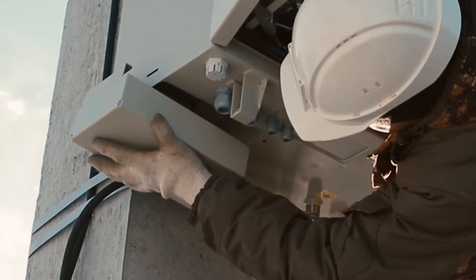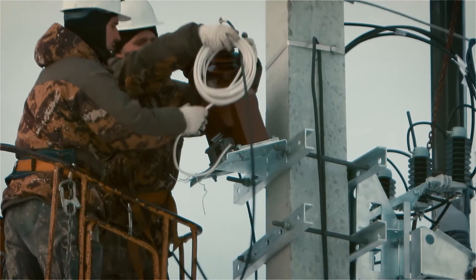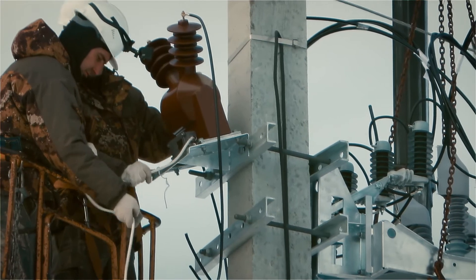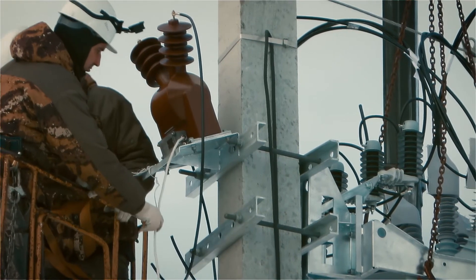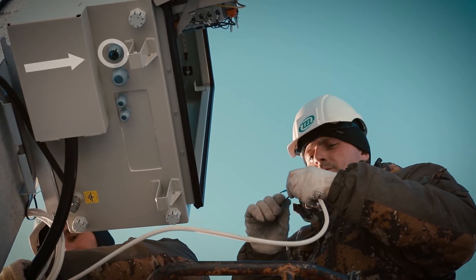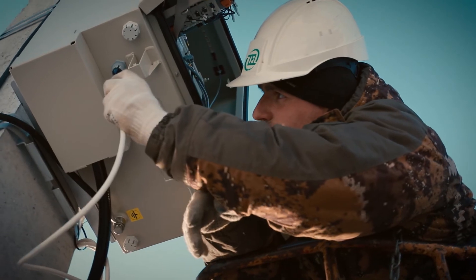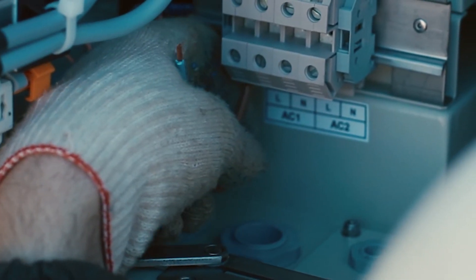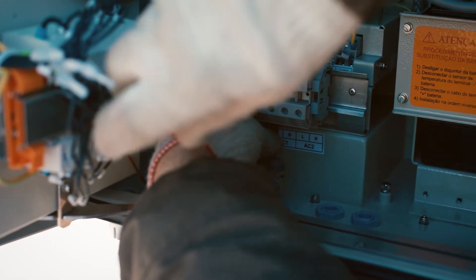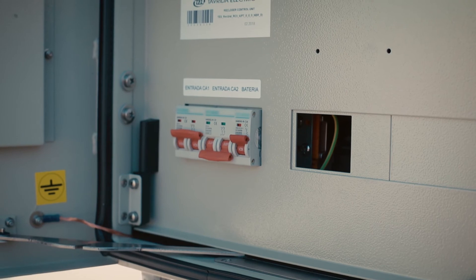Put the anti-vandal cover back on and fasten the captive screw from inside of the RC. To connect the auxiliary power supply cable to the VT, use the terms and regulations provided by the VT manufacturer. The other end of the cable should be inserted into the RC through the cable gland located at the bottom of the RC. Connect the cable to the power supply module according to the handling and installation guide.